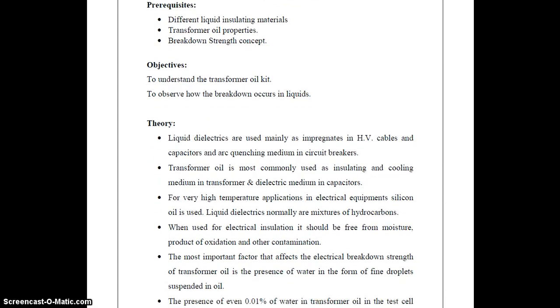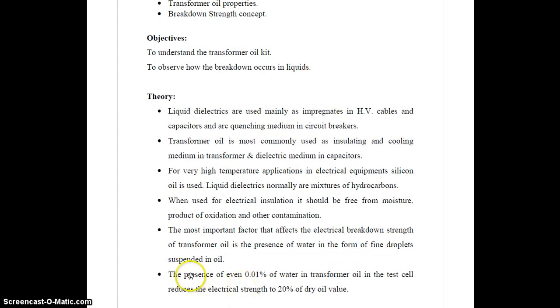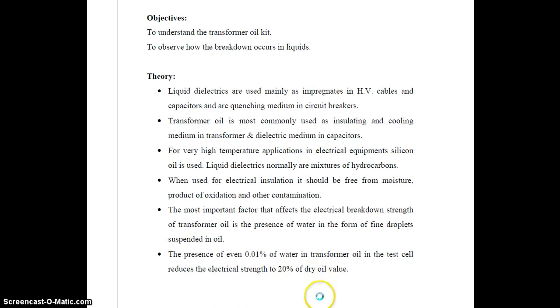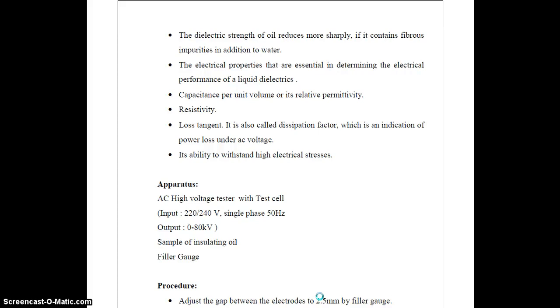The most important factor that affects the electrical breakdown strength of transformer oil is the presence of water in the form of fine droplets suspended in oil. The presence of even 0.01% water in transformer oil in the test cell reduces its dielectric strength to 20% of the dry oil value. The dielectric strength of oil reduces more sharply if it contains fibrous impurities in addition to water. Then the electrical properties that are essential in determining the electrical performance of liquid dielectrics.